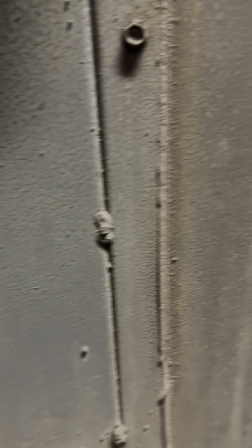It's actually been pretty good lately, because the first couple years I worked here, I remember changing all these filters and they were spanking white, and a week later we lost static pressure. I'm thinking, how can you lose static pressure, they're clean filters? I looked through the window and the filters were absolutely white - that year we had a really bad pollen year and it plugged my filters within a week.